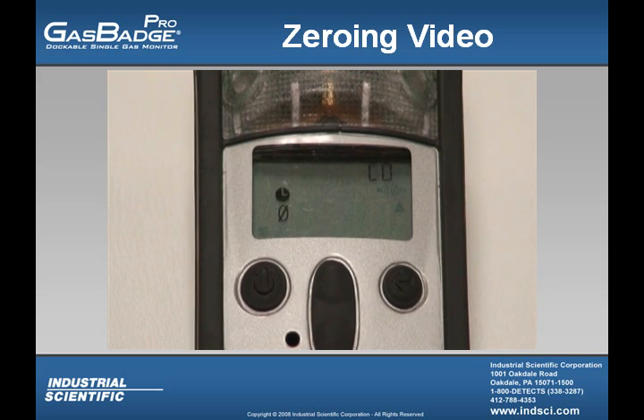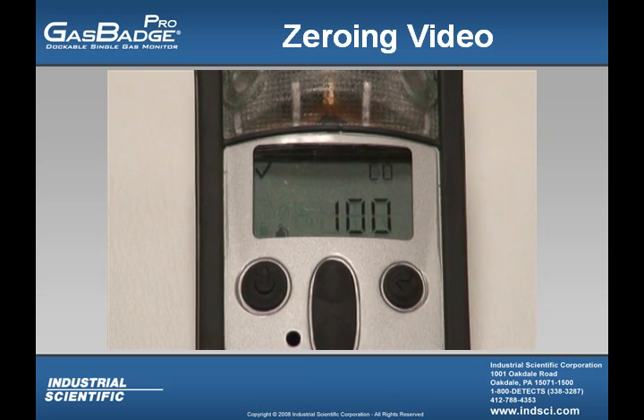After the zeroing process is done, you're going to see a check mark in the upper left-hand corner, and the instrument is going to emit a short beep. From there, the instrument is going to ask you if you want to go into a calibration mode. What you're going to want to do from here is either press the on-off button or let the instrument time out. And in this instance, we're actually going to let the instrument time out.